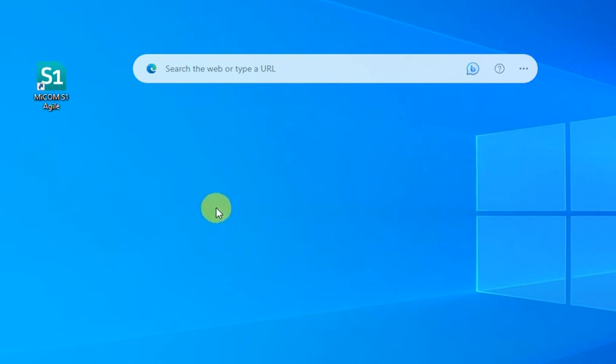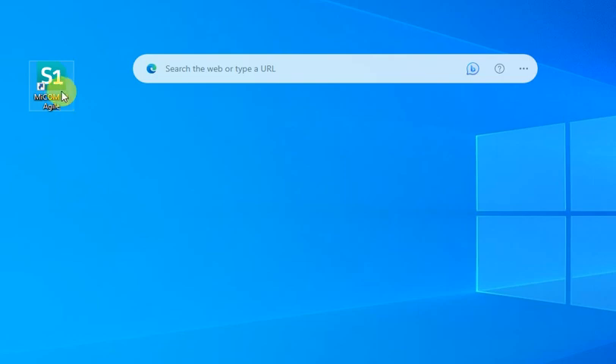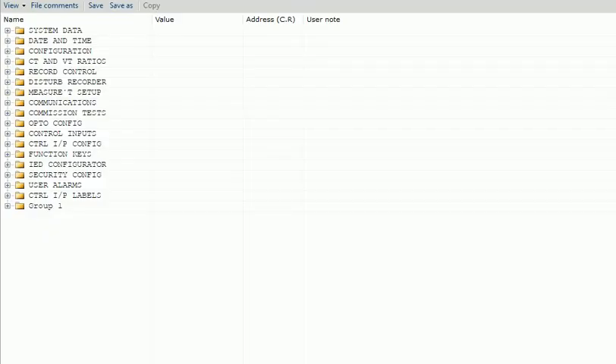If you have the MiCOM S1 Agile software in your system, just open it and open your scheme drawing. After opening the software, you can see here the system data, date and time, configuration, CT and VT ratio, record control — these parameter settings will be available in the P643 relay.